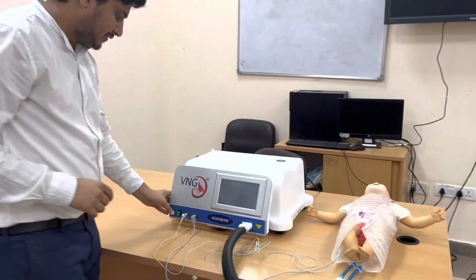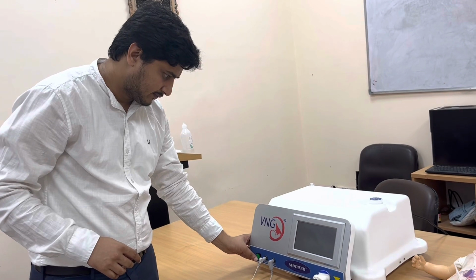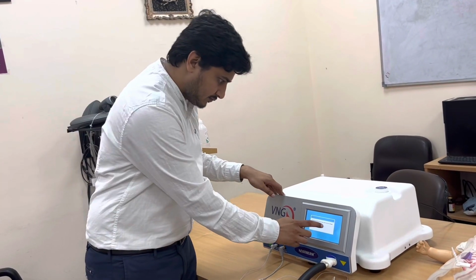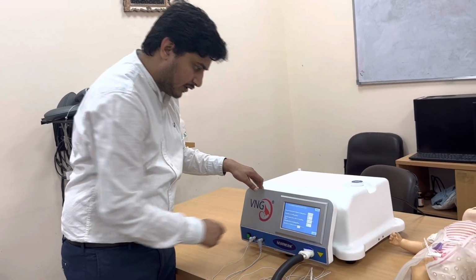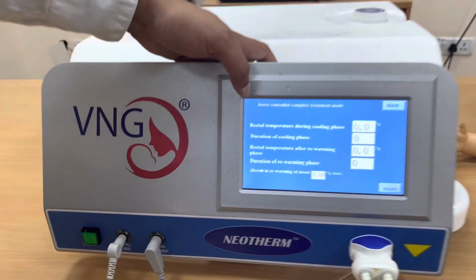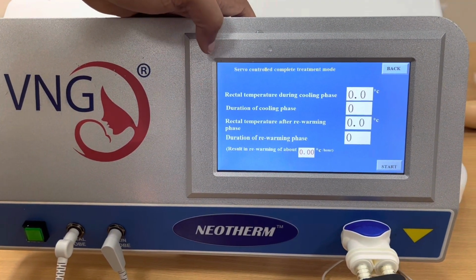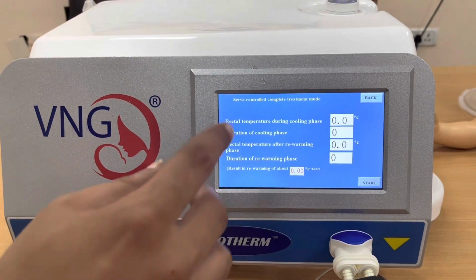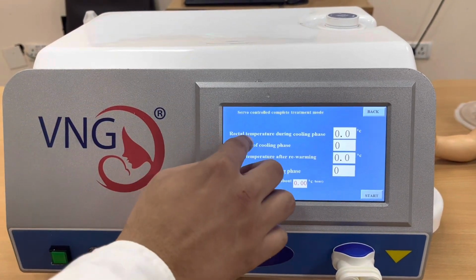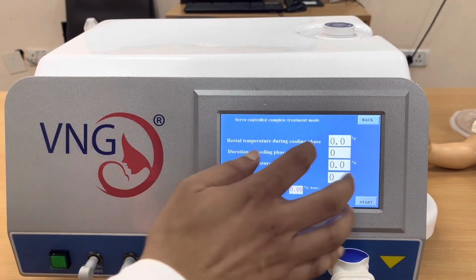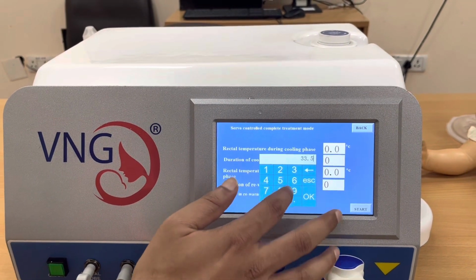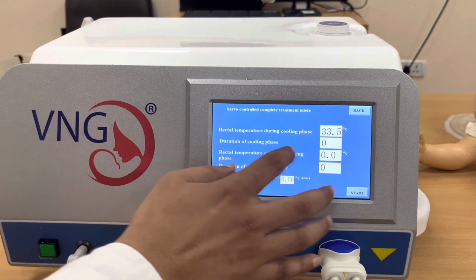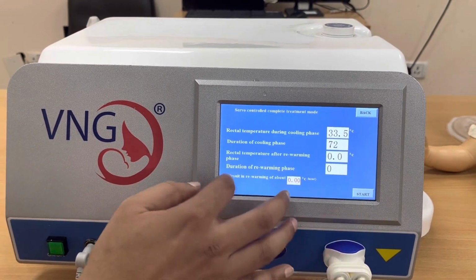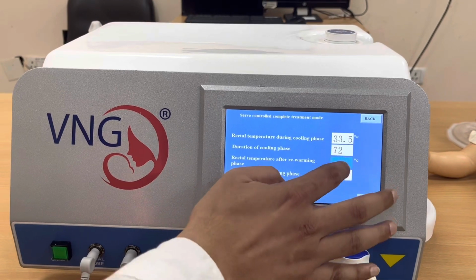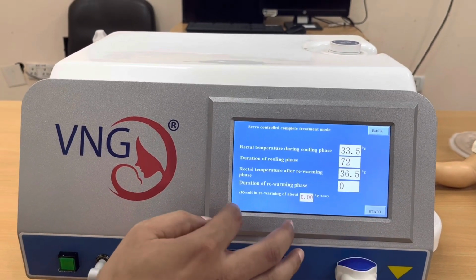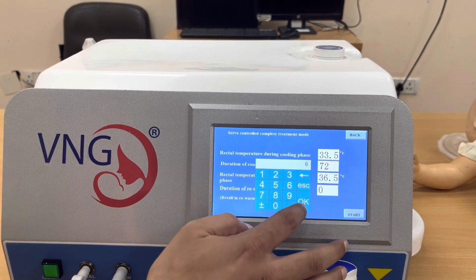You have to switch on the device. Here you can see that once we have switched on the device, the machine displays a panel. Here we have to set the temperature parameters. The rectal temperature during the cooling phase, that is the target core temperature, should be set at 33.5 degrees Celsius, which is the standard recommendation. The duration of the cooling phase is 72 hours. The rectal temperature after the rewarming phase should be set at 36.5 degrees Celsius, and the duration of the rewarming phase ranges from 6 to 8 hours as per the recommendations.